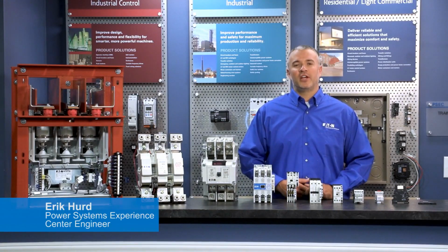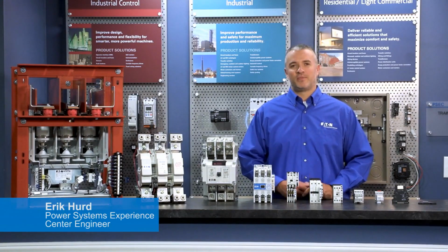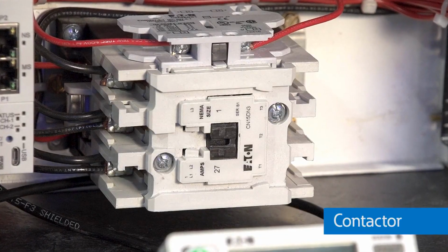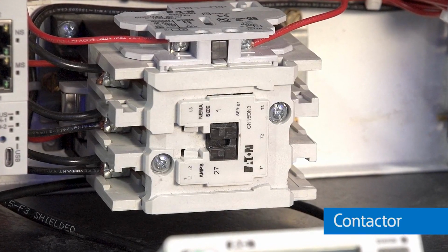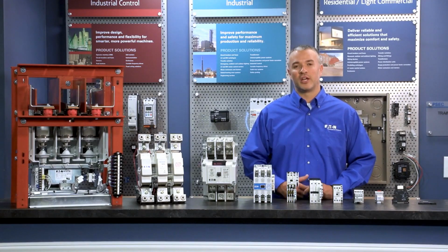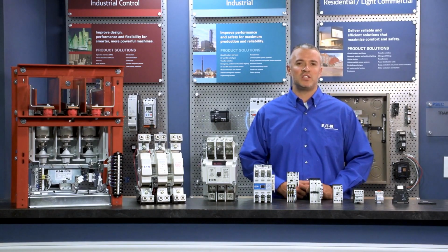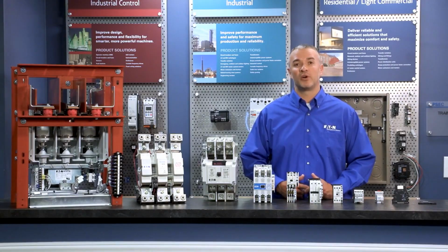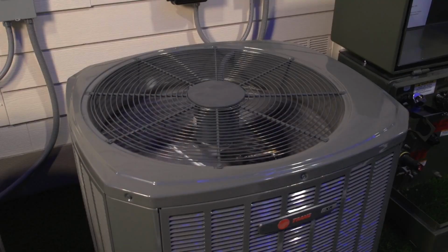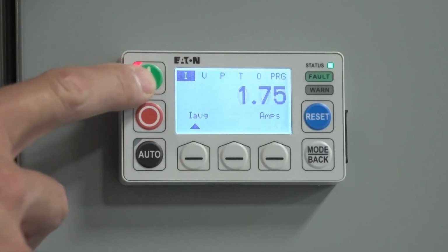So what is a contactor and where are they typically applied on an electrical system? A contactor is an electrically controlled switch used for switching a power circuit with a lower power level control circuit. For example, using 24 volts DC to control a 480 volt AC motor. Contactors are typically used to switch high current load devices such as motors, heating, air conditioning, lighting, capacitor banks, and transformer switching that can be controlled either locally or remotely by manual or automatic control devices. Contactors are also commonly used in transfer switches.